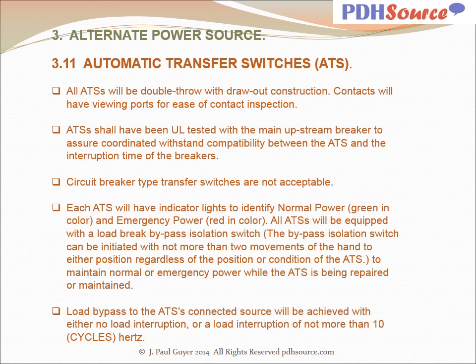All ATSs will be equipped with a load break bypass isolation switch. The bypass isolation switch can be initiated with not more than two movements of the hand to either position, regardless of the position or condition of the ATS, to maintain normal or emergency power while the ATS is being repaired or maintained. Load bypass to the ATS's connected source will be achieved with either no load interruption or a load interruption of not more than 10 cycles per second or hertz.